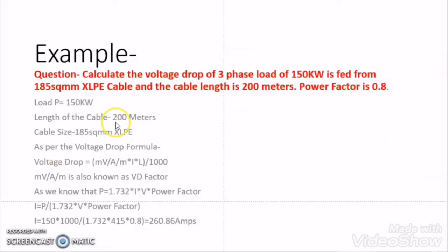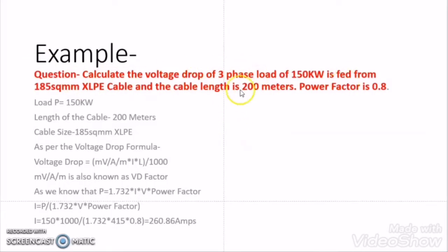Let us take one example to understand this topic very clearly. Calculate the voltage drop of a 3-phase load of 150 kW, fed from a 185 square mm XLPE cable. The cable length is 200 meters and the power factor is 0.8. First of all, collect the information available from the question: this is a 3-phase load, the load P = 150 kW, length of cable = 200 meters, and cable size is 185 square mm XLPE.